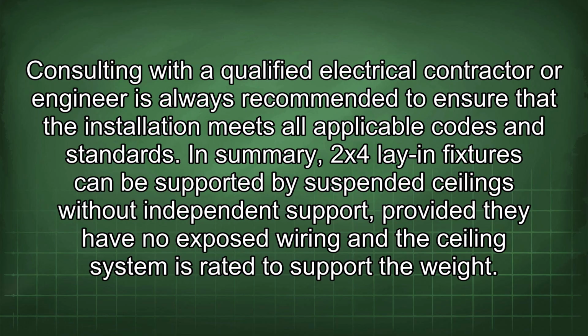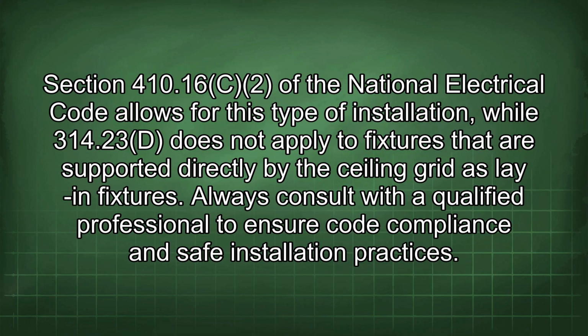Consulting with a qualified electrical contractor or engineer is always recommended to ensure that the installation meets all applicable codes and standards. In summary, 2x4 lay-in fixtures can be supported by suspended ceilings without independent support, provided they have no exposed wiring and the ceiling system is rated to support the weight. Section 410.16c2 of the National Electrical Code allows for this type of installation, while 314.23d does not apply to fixtures that are supported directly by the ceiling grid as lay-in fixtures. Always consult with a qualified professional to ensure code compliance and safe installation practices.